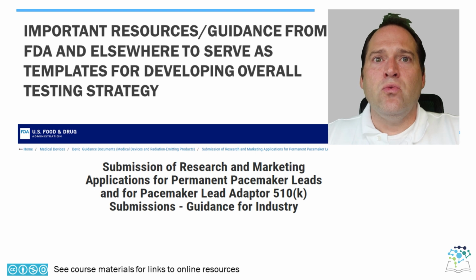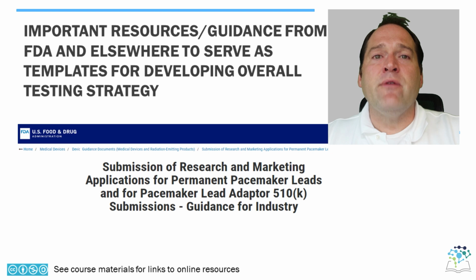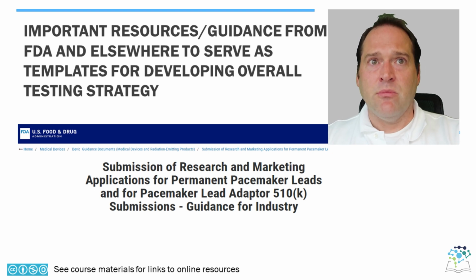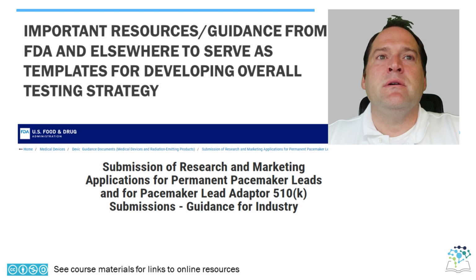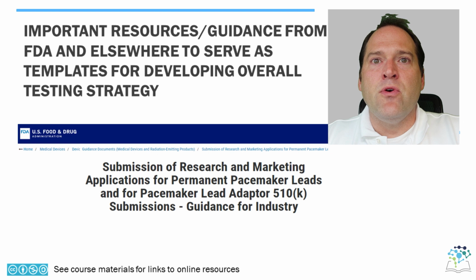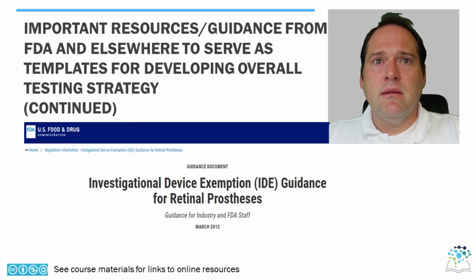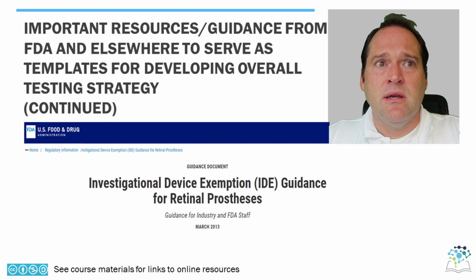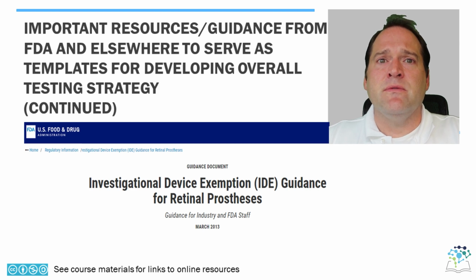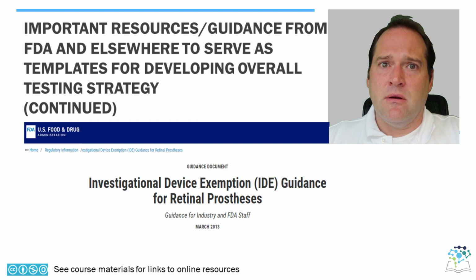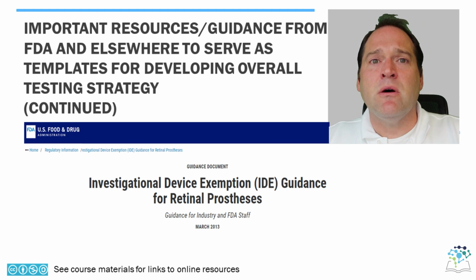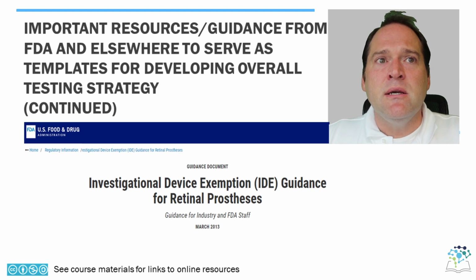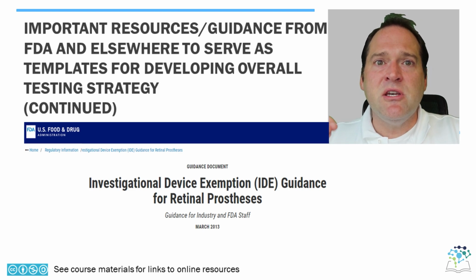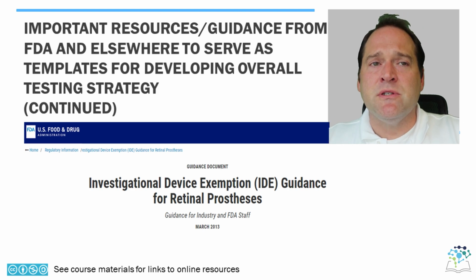So I've outlined two really good templates for your failure modes analysis and for the testing that's typically used to address that failure modes analysis. One of the most important is a guidance, and the link is on the slide, for the research and marketing applications for permanent pacemaker leads and for pacemaker lead adapters. The second guidance that I've included is the retinal prosthetics guidance. And this is really useful because it's a more complicated system in terms of how the retinal prosthetic works. There are wireless components that are talking to each other to inform neural stimulation parameters based off of camera readings and things like that. So these are, to some extent, similar devices to the cardiac pacemaker, but they have some technology differences that are important to be aware of.